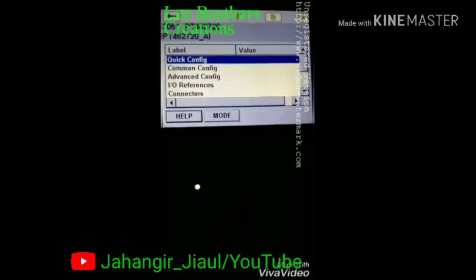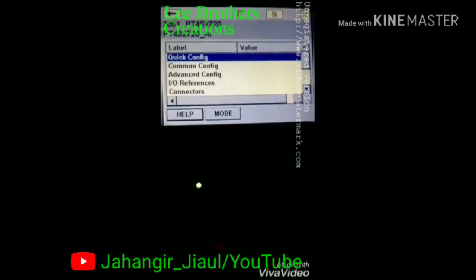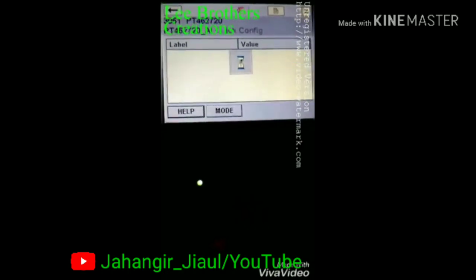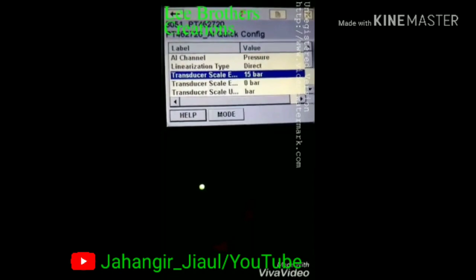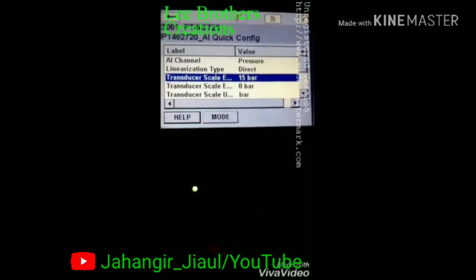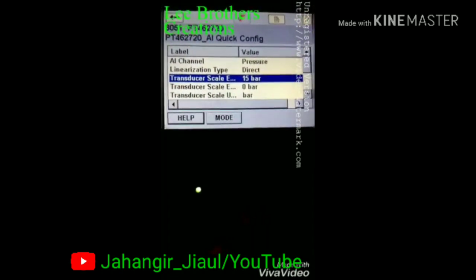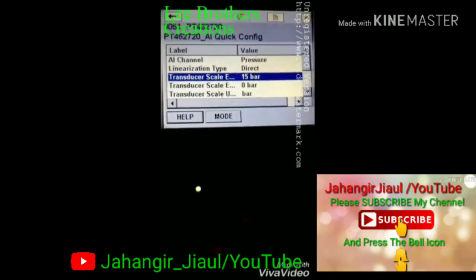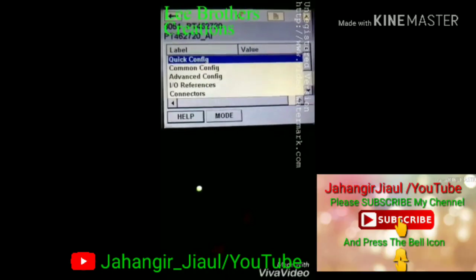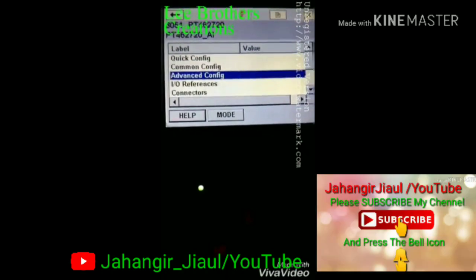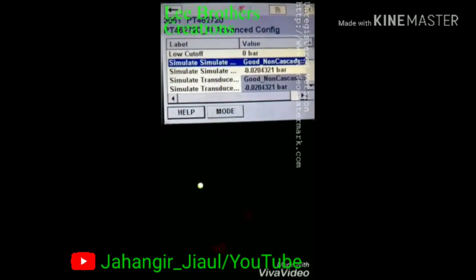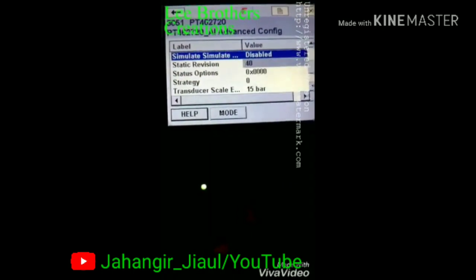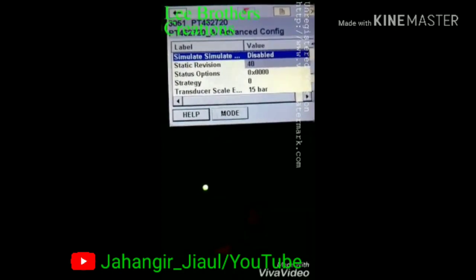To set the range of this transmitter, we enter the quick config, which shows some parameters. The range of this transmitter is 0 to 15 bar, with a URV and LRV. Then come back to the platform and go to the analog input config. Here you select simulation — enable and disable.